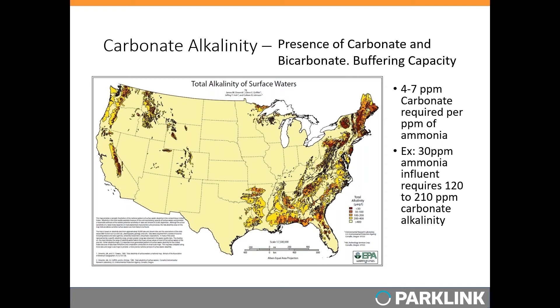Alkalinity is essential for autotrophic nitrifiers since carbonates and bicarbonates are their carbon source, and the alkalinity helps neutralize acids produced in the first step of nitrification — the oxidation of ammonia to nitrite. Nitrifiers typically need 4–7 parts per million of carbonate per 1 part per million of ammonia entering the plant. For a standard municipal plant receiving 30 ppm of ammonia in the influent, that requires about 120–210 ppm of alkalinity. An EPA map shows carbonate alkalinity of surface water across the country, illustrating that different areas may have lower carbonate alkalinity, which can negatively affect nitrification.